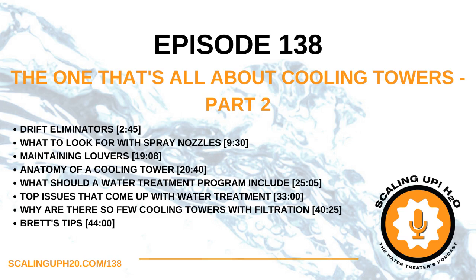Typically, when those units are outside, you'll see them with a spray pump right by the unit, connected to a piping that goes up the side of the unit called a riser pipe. That's what transports the water out of the basin up to the top of the unit and then sprays it over the coil. So what we see a lot is people trying to tap off that riser pipe to bring supply water to a conductivity manifold or a supply line to then inject some chemicals into it.